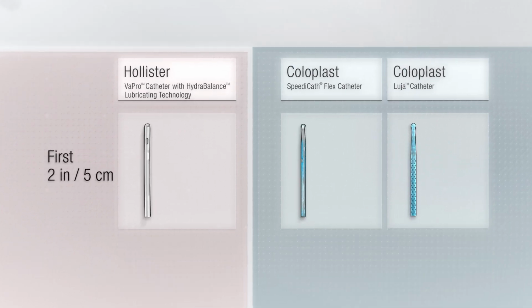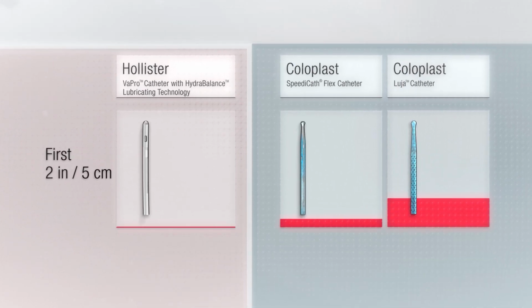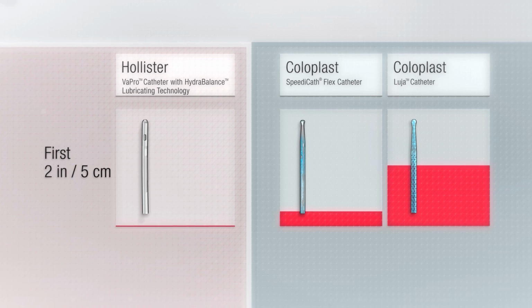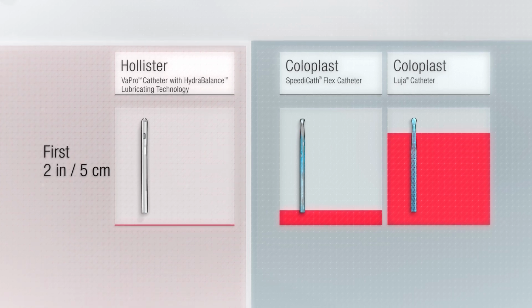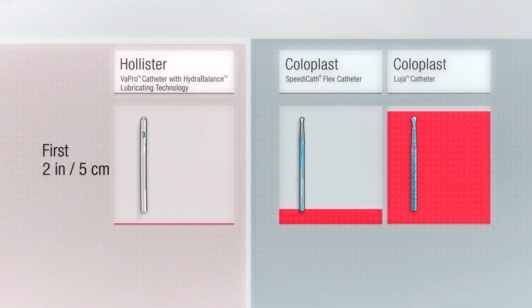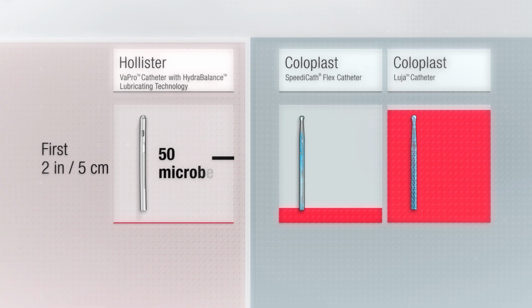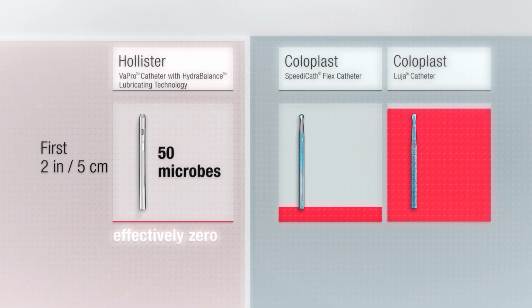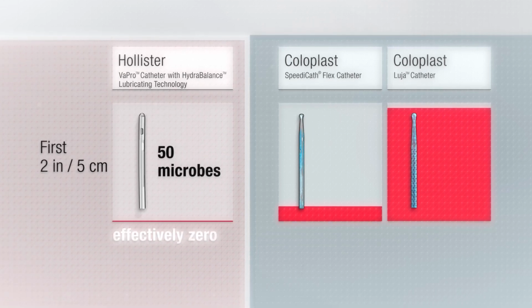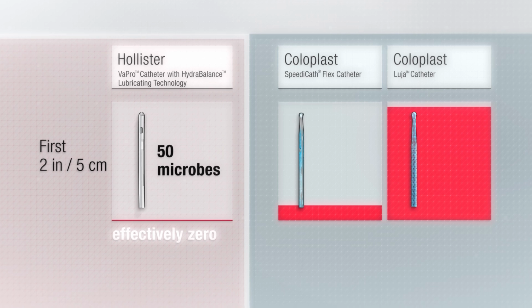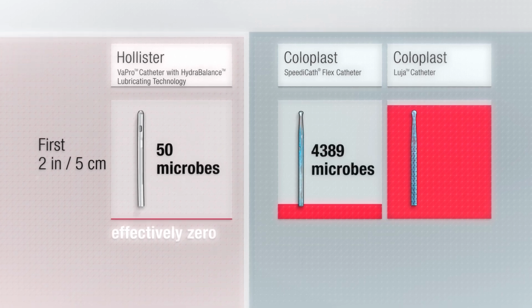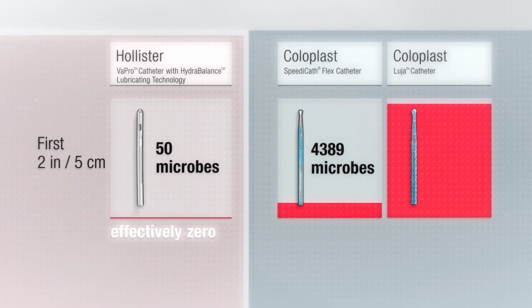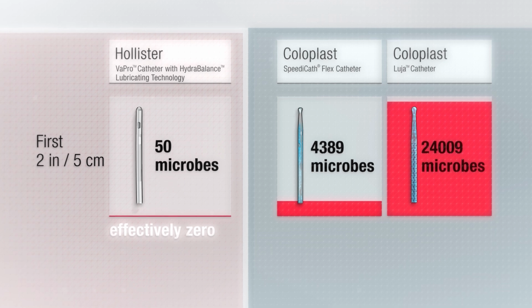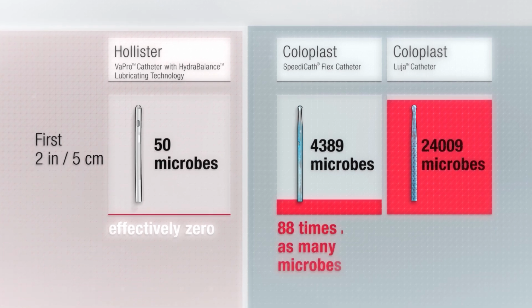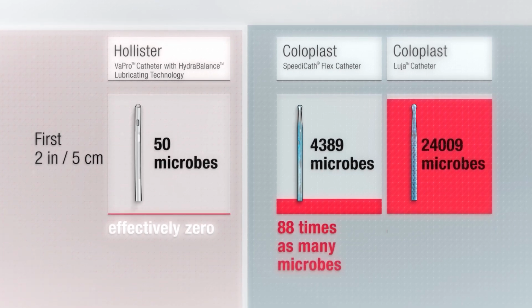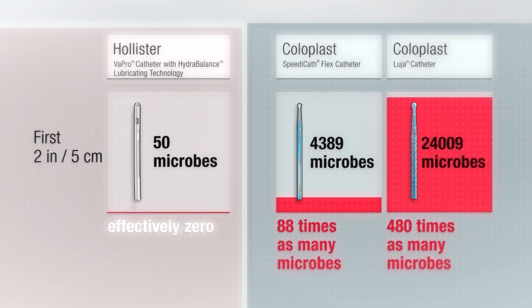If you compare the segments of each catheter after they had been pushed through the urethral model, there were differences. VaPro catheters provided superior protection in reducing microbial contamination to effectively 0. On average, microbial contamination was significantly greater for both SpeediCath Flex catheters and Luja catheters compared to VaPro catheters in the first 5 centimeter segments of the catheters.